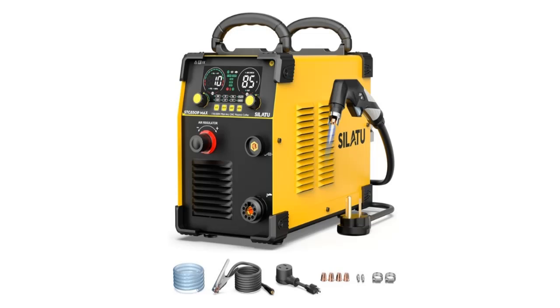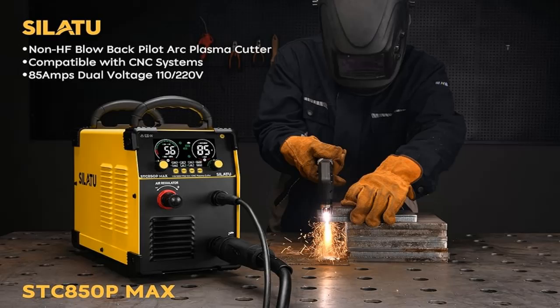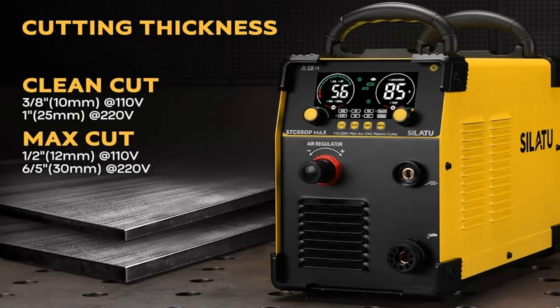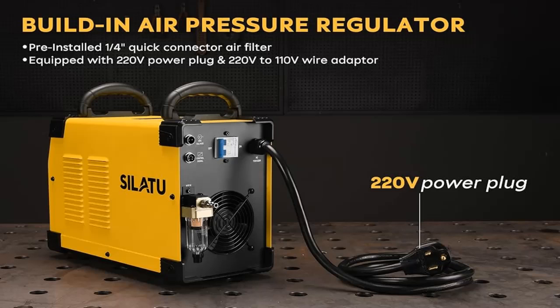Air sensor technology. An integrated air sensor displays the air pressure on the machine's front panel. Users can manually adjust the air pressure using the air regulator, as automatic adjustment is not available. An air filter is installed at the rear of the unit, featuring a quick connect 1/4 NPT air fitting for easy setup. When connected to an air compressor, the recommended air pressure should be set to around 65 psi, with a flow rate of approximately 250 liters per minute.